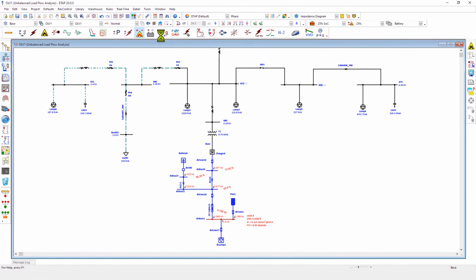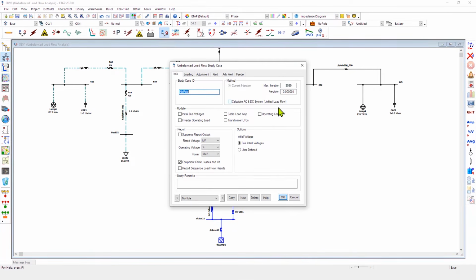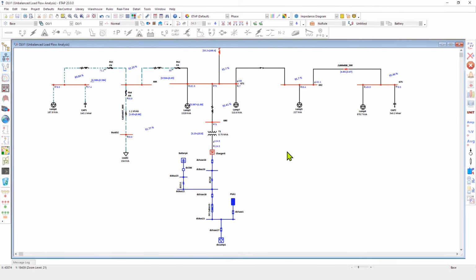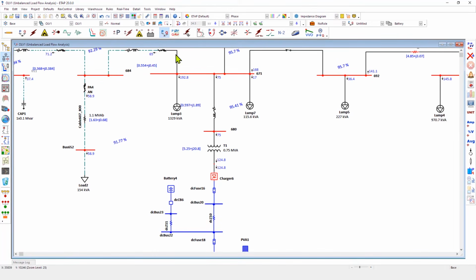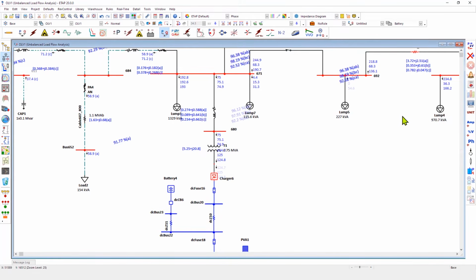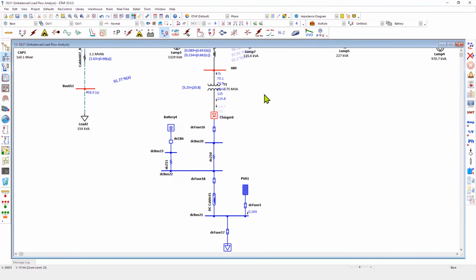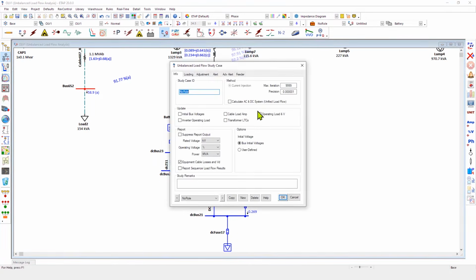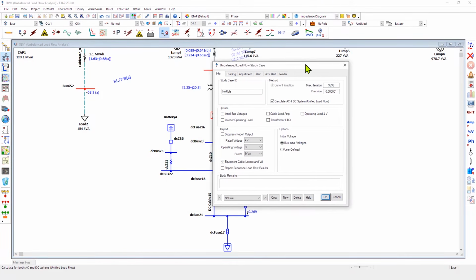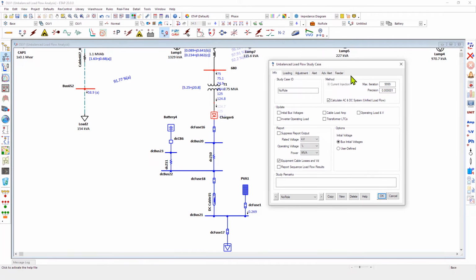DC computation. ETAP unbalanced load flow in fact is a unified load flow that allows you to run AC and DC systems together. For those of you who are using unbalanced load flow, you are running calculations primarily on the AC system, where you can observe the per phase values of voltage, current, as well as the neutral current and other parameters. When this unbalanced load flow is combined with the power of the DC system or the DC network, we are essentially running a unified load flow, where ETAP solves unbalanced power flow on the AC network combined with the DC network simultaneously. These calculations are run together at the same time and not iteratively between the AC and DC network.